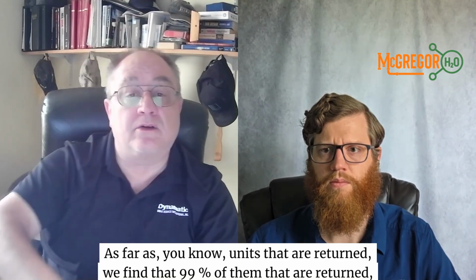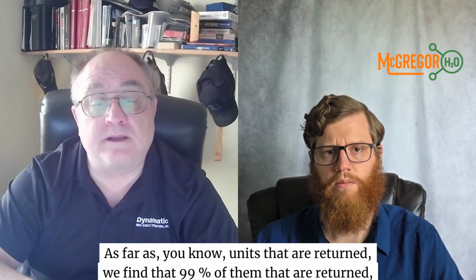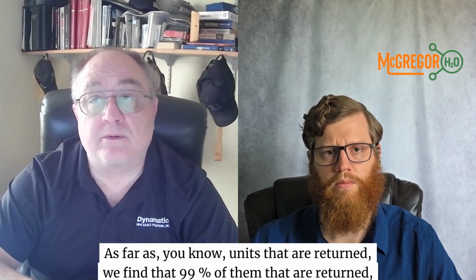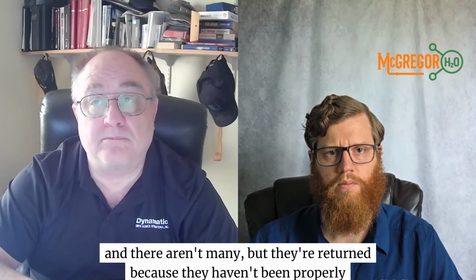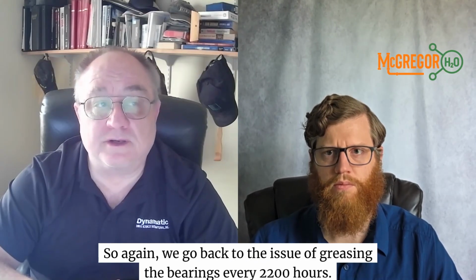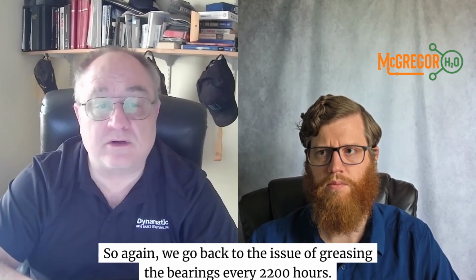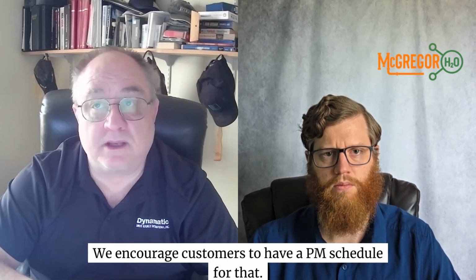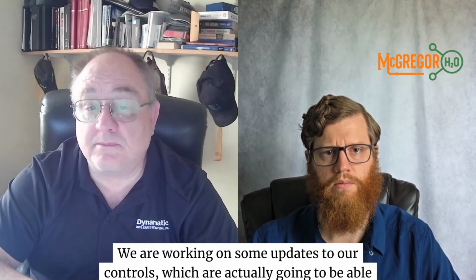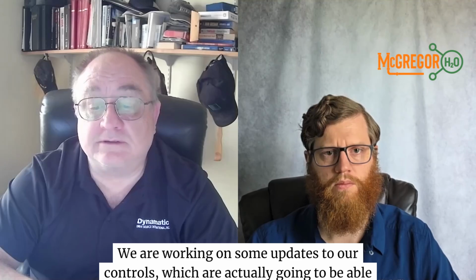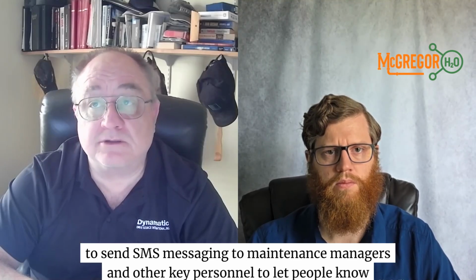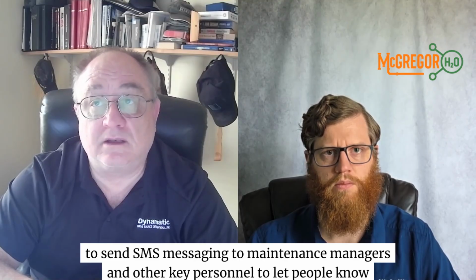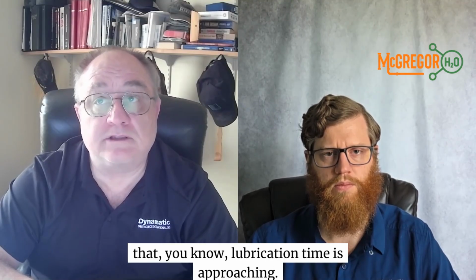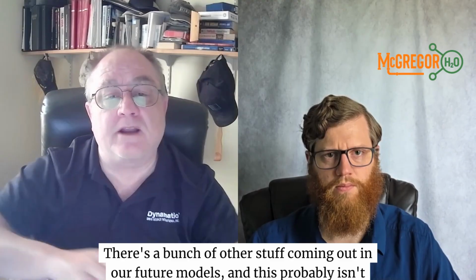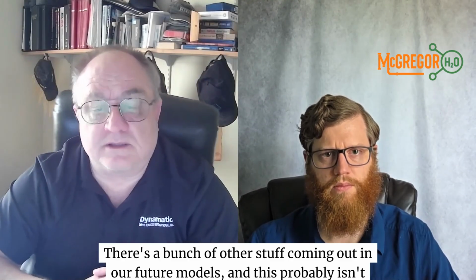As far as units that are returned, we find that 99% of them that are returned, and there aren't many, are returned because they haven't been properly lubricated. So again, we go back to the issue of greasing the bearings every 2,200 hours. We encourage customers to have a PM schedule for that. We are working on some updates to our controls, which are actually going to be able to send SMS messaging to maintenance managers and other key personnel to let people know that lubrication time is approaching. There's a bunch of other stuff coming out in our future models, and this probably isn't the right time for it, but it is coming.